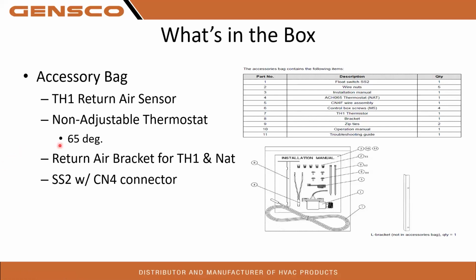In the package, you'll have a couple of thermistors. You have a return air thermistor, which is this larger one with a bare copper end on it. And then also a non-adjustable thermostat that's set for 65 degrees. And that is this thermostat right here. It's got a red cover over the end of it. Both of those, the return air temperature thermistor is going to be an important one. You'll have to use that. The non-adjustable thermostat will be used if you're using a Mitsubishi stat or a non-24 volt stat. And we'll get into that more in a little bit.